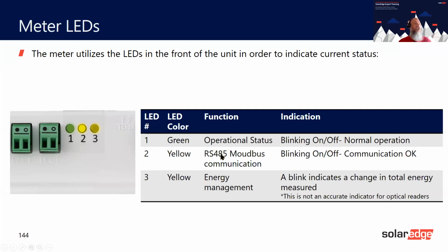Number two, yellow, which it is, and it's for RS485 communication. That means that you're getting communication with the inverter. And number three, this one here, is energy management. A blink indicates the total energy is measured. So it's actually measuring. So you can see on here that it's measuring the CT. So that's good.